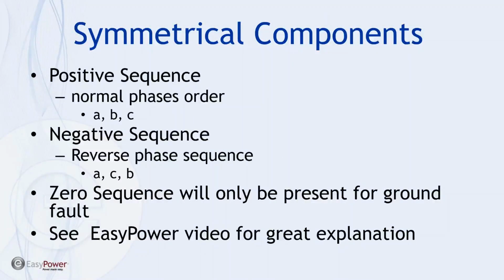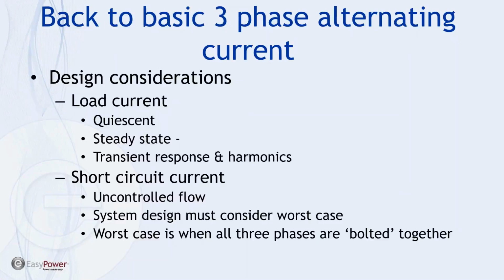in passing. And it brings us back to the basic three-phase alternating current discussion, which is where we titled this symmetric and asymmetric fault currents. Anytime we're looking at an electrical system, there's basically two currents that we're concerned about. The first is load current, which is normal operations in quiescent and steady state. And there are times that we want to look at transient response and harmonic response of these considerations.